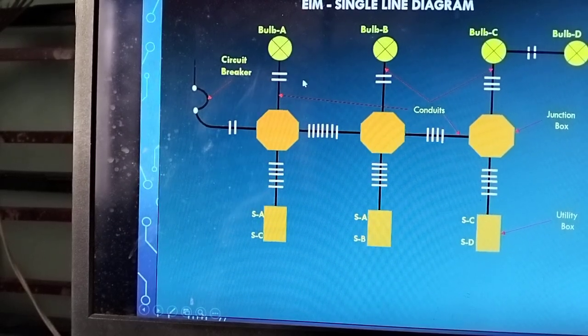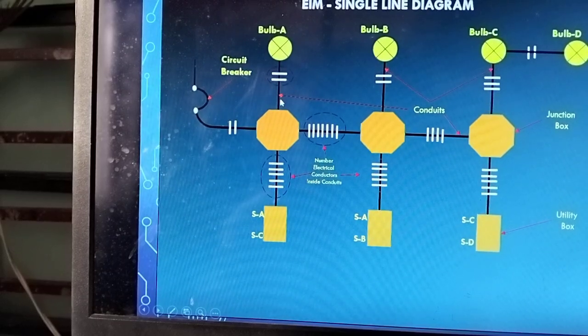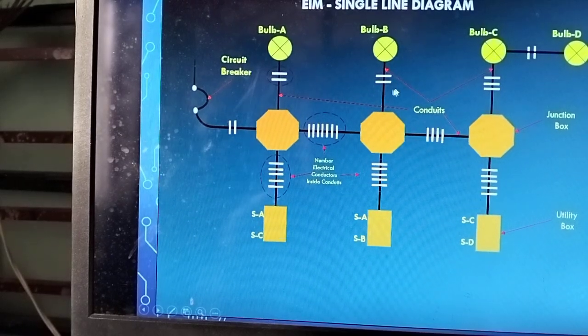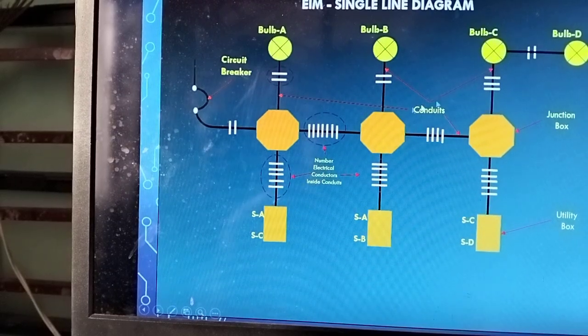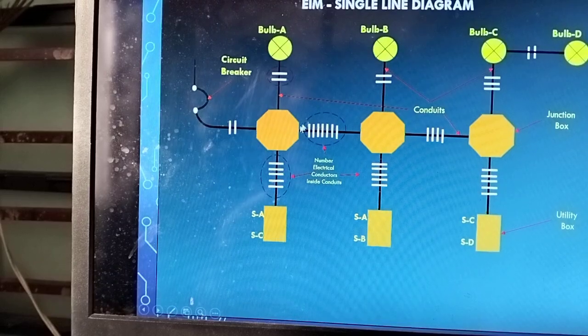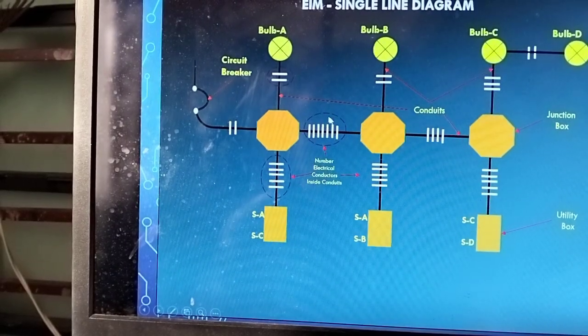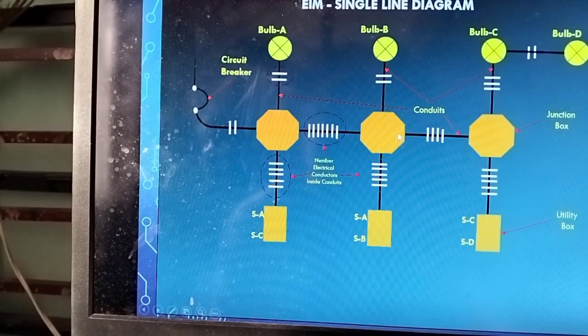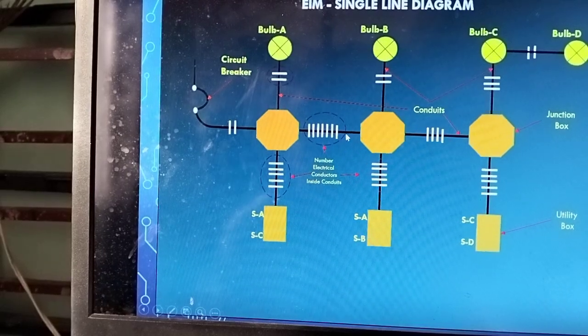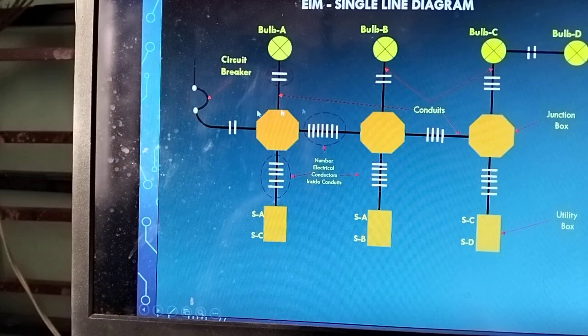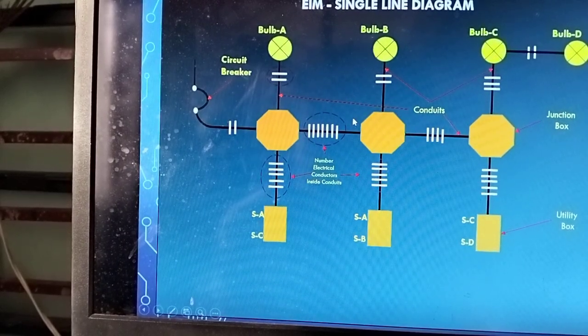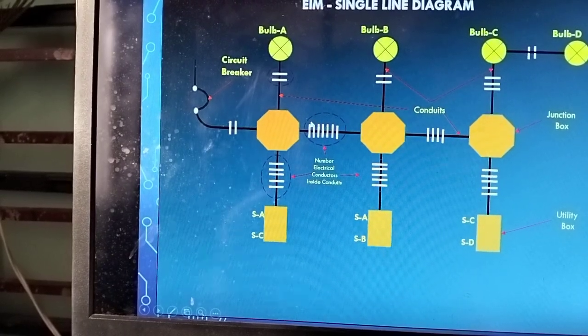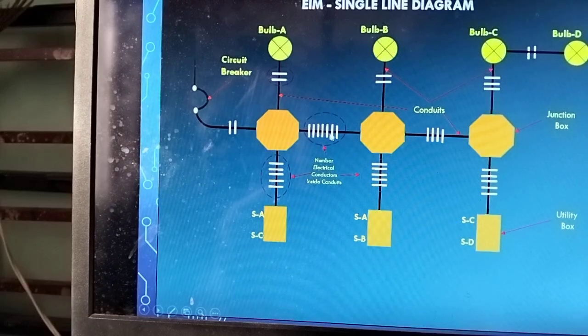This slash represents the number of individual conductors. Let's say here it has a maximum of 2, so you can use size 1/2 PVC conduit, because it has a minimum number of wires. See, 2, 2, 3, 3, 2. Whereas in this portion it has 7 individual conductors, so it's quite difficult if the distance of this junction box is very far, very long, to use size 1/2 conduit. Better make it 3/4 size, so it can easily accommodate the electrical wires. Let's say this is 7 wires.